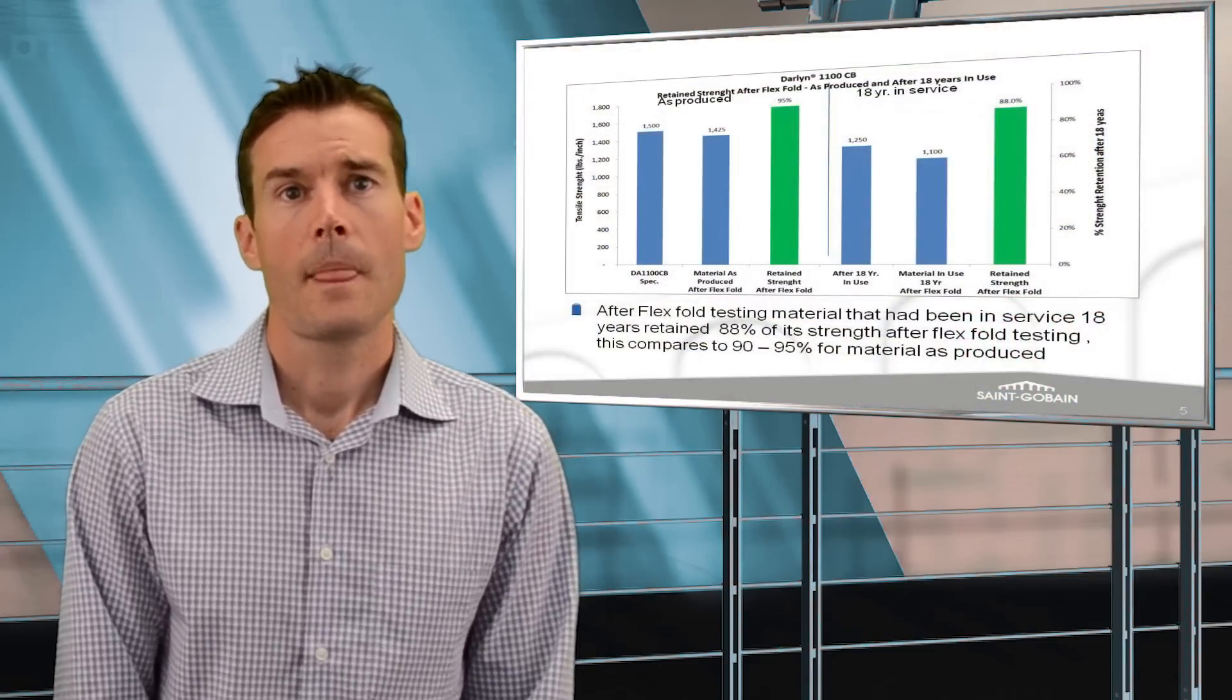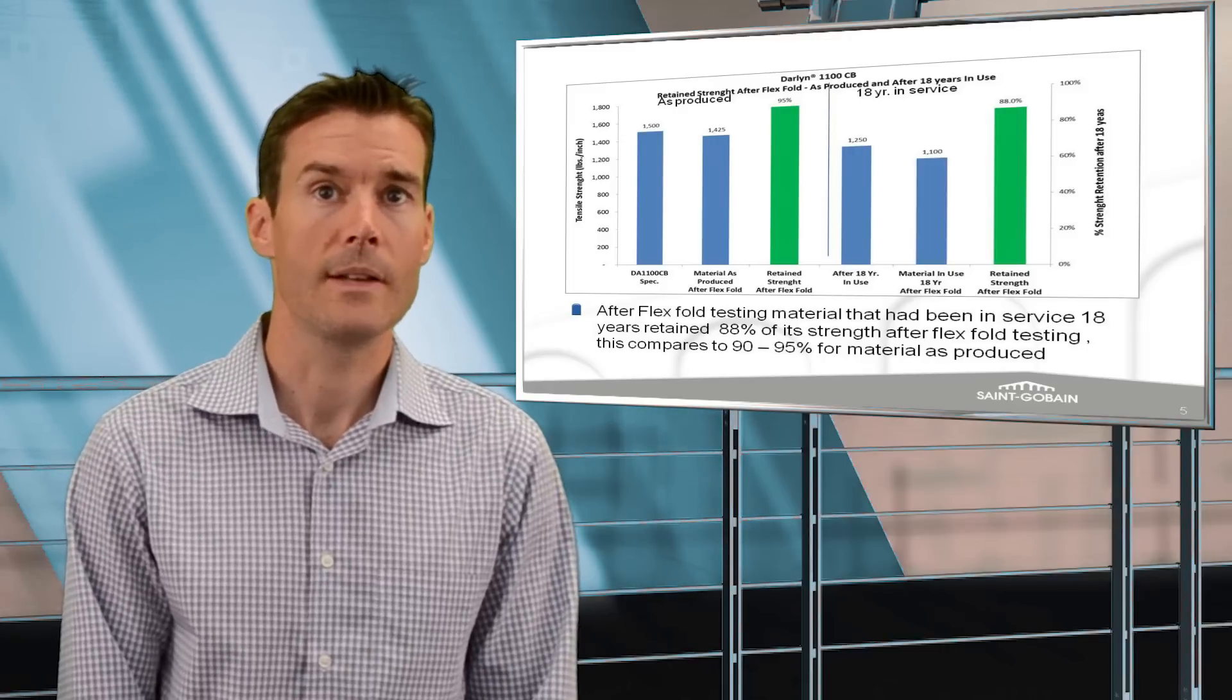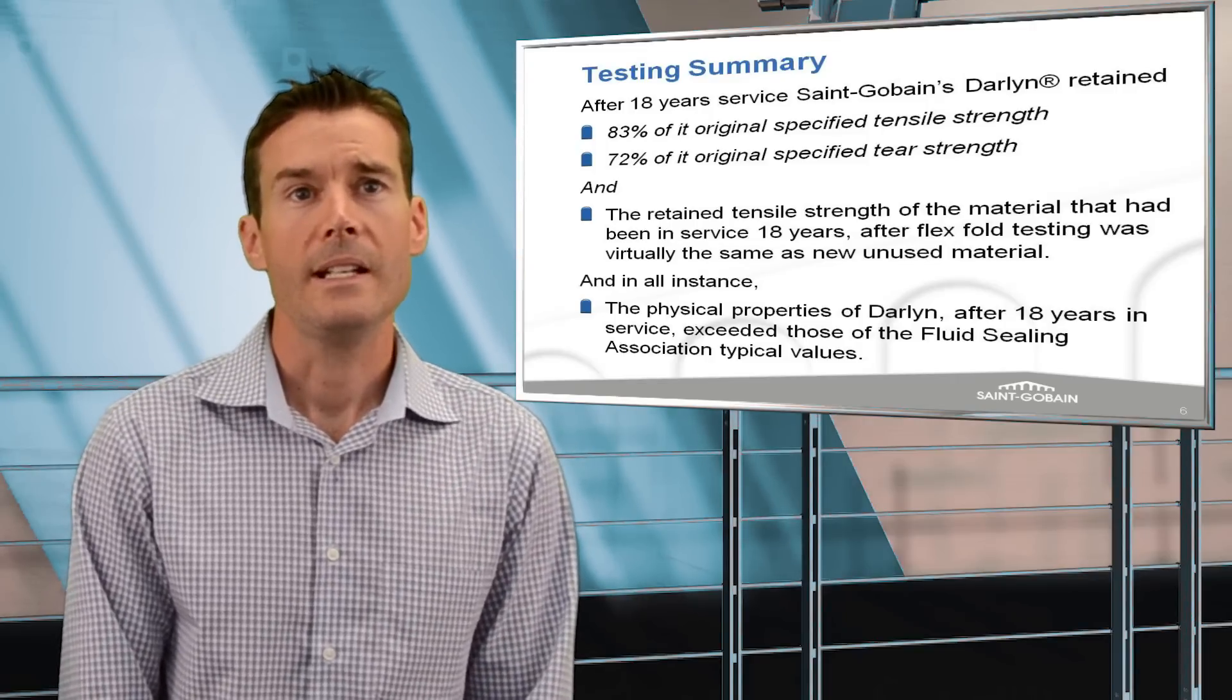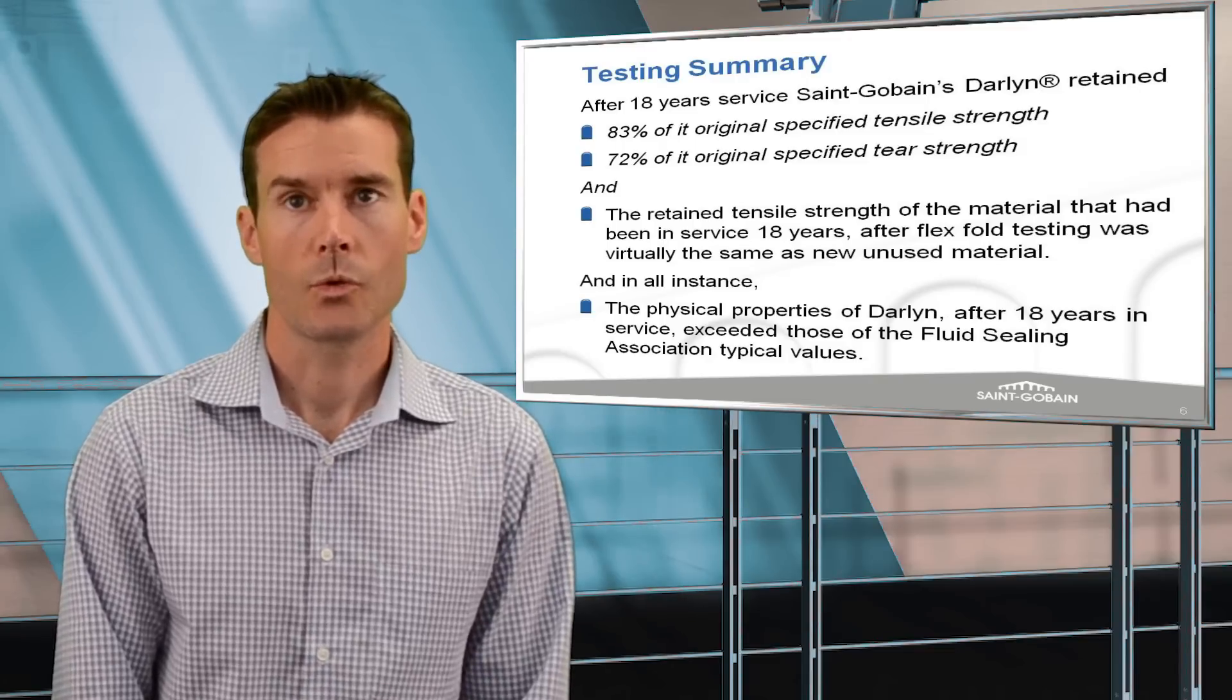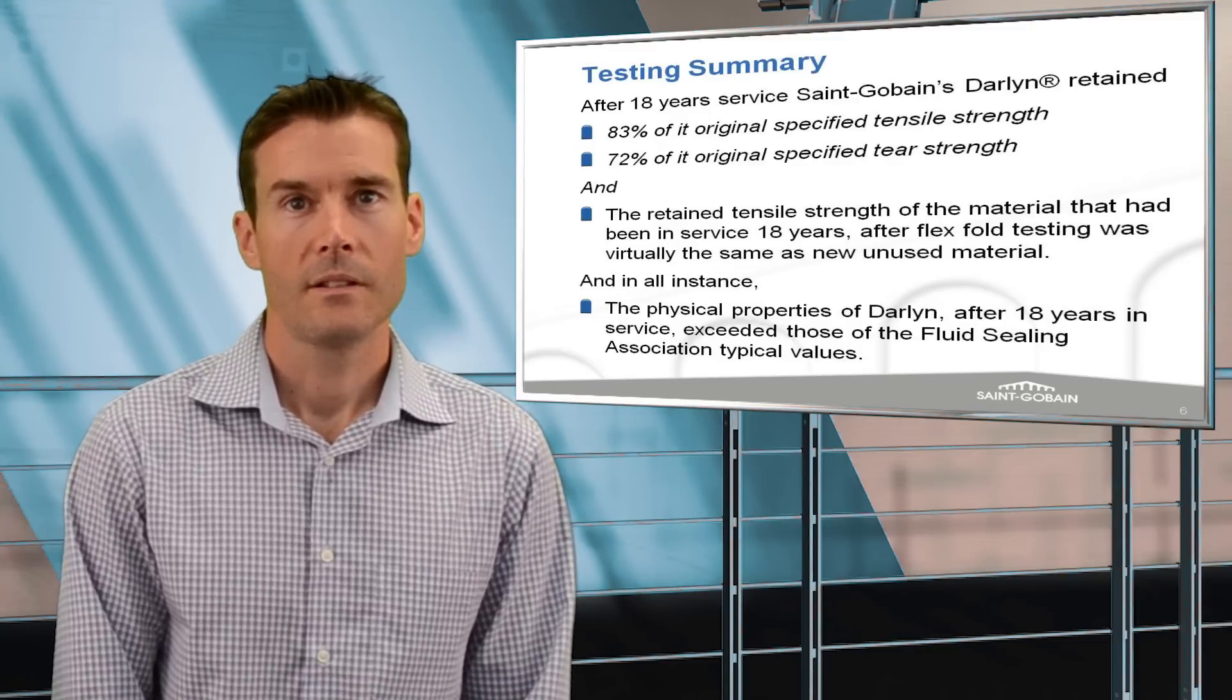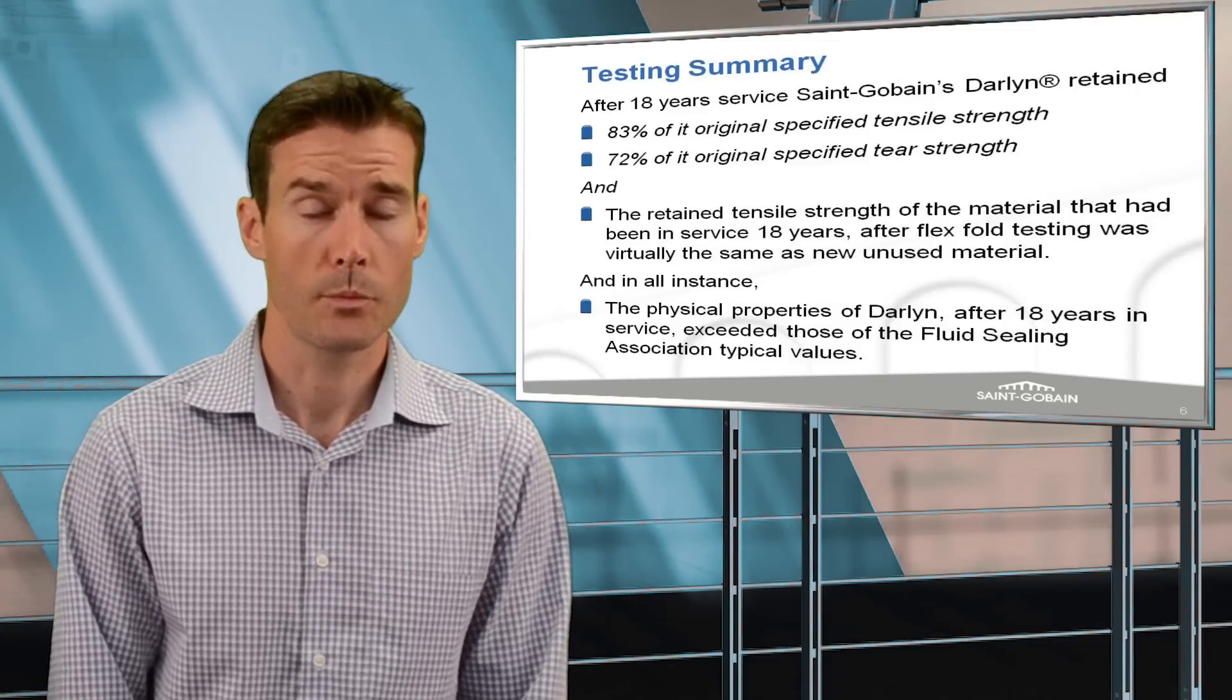Lastly, the retained tensile strength after flex-fold testing was virtually unchanged from the retained strength that is typical for the Darlyn material as originally produced. In summary, this 18 years of service Darlyn retained 83% of its original tensile strength, 72% of its original trapezoidal tear strength, and all of its retained tensile strength after flex-fold testing. Finally, all physical properties of the Darlyn material exceeded those of the fluid sealing association's typical required values for these properties.